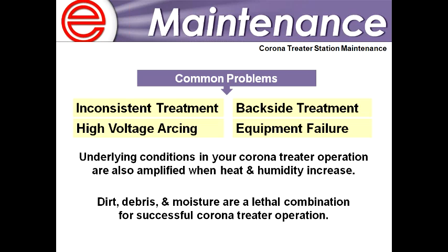As heat and humidity increase, there can be a lot of underlying problems that become amplified. You can think of it this way: the high voltage is going to look for the shortest path to ground. The reason I mention that is, there may be some high voltage wiring that's too close to ground, or things like that. When you get moisture, moisture and dirt and debris don't mix very well with high voltage, because that high voltage is going to find a shorter path to ground and arc through that. What I mean is that it's going to create a spark, and it's going to lead to equipment damage for the most part. It shortens the life of the insulating shroud, the life of electrodes, and things like that.